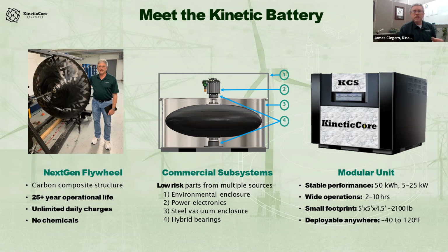Each one of our modular units has a very small footprint, about 5 foot by 5 foot, that can be put in rows and scaled up to whatever is required at the customer's site. The other advantage is that we can be deployed essentially anywhere. Our temperature range is -40 to 120 degrees Fahrenheit, so we can be deployed in cold regions, hot regions.